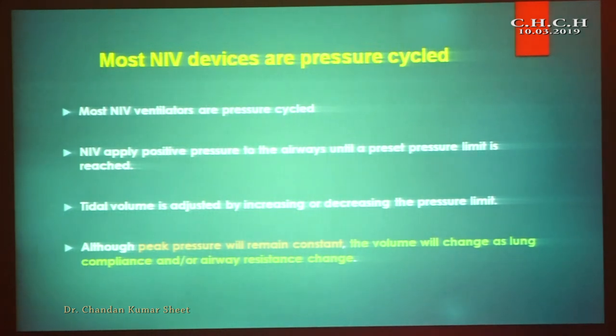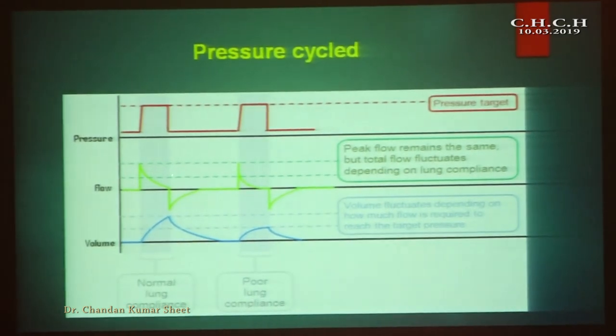Most NIV devices are pressure cycled, meaning inspiration and expiration have two fixed pressures that the machine delivers to provide the tidal volume. However, depending on the patient's lung compliance and airway resistance, the peak pressure is always fixed but the compliance and the delivered volume will change. In a normal lung the volume is high, while in poor lung compliance the volume is decreased, but the peak pressure remains the same.